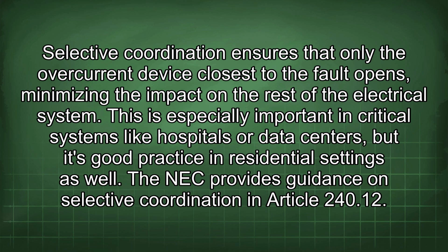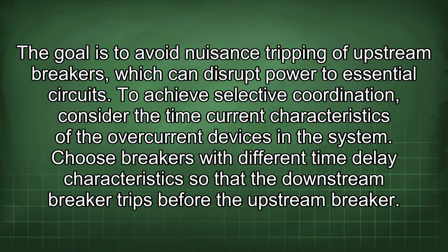Selective coordination ensures that only the overcurrent device closest to the fault opens, minimizing the impact on the rest of the electrical system. This is especially important in critical systems like hospitals or data centers, but it's good practice in residential settings as well. The NEC provides guidance on selective coordination in Article 240.12. The goal is to avoid nuisance tripping of upstream breakers, which can disrupt power to essential circuits.